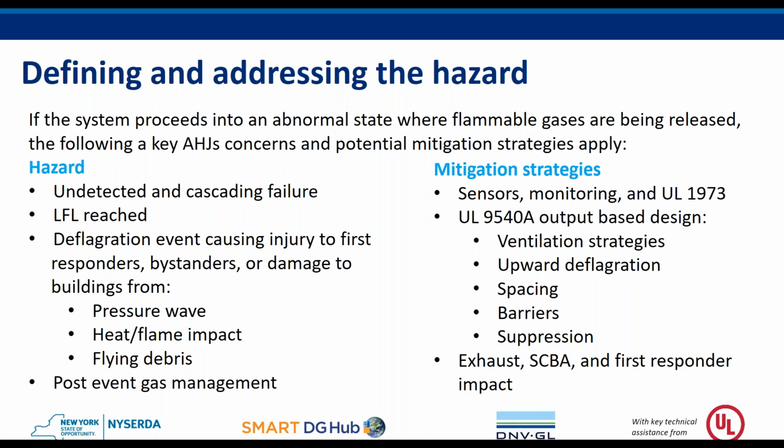Second, if it's cascading, there are going to be gases released from the batteries failing, and those gases may end up having local concentrations where the lower flammability limit is reached. If that occurs, there's a risk of an explosion, in which case that explosion or deflagration event could cause injury to people who are in the facility or near the building or who are responding to an event, either by pressure, heat, or flying debris. And then finally, after the situation is essentially managed, there still may be trapped gases in the area.